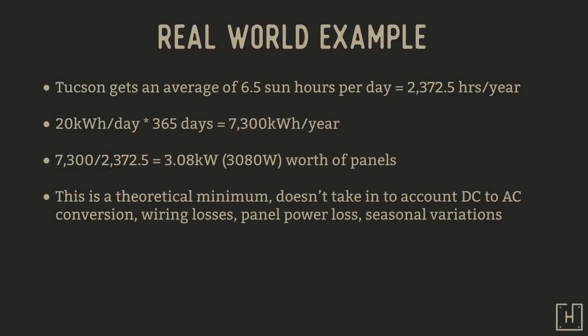Real world example: Tucson gets an average of about 6.5 sun hours per day, which equals 2,372 hours per year. Say we're using our example of 20 kilowatt hours per day, multiply that by 365 days, that's 7,300 kilowatt hours per year. Take those two numbers, 7,300 divided by 2,372, and that means we're going to need approximately, and I say approximately for a reason, 3.0 kilowatts worth of panels.